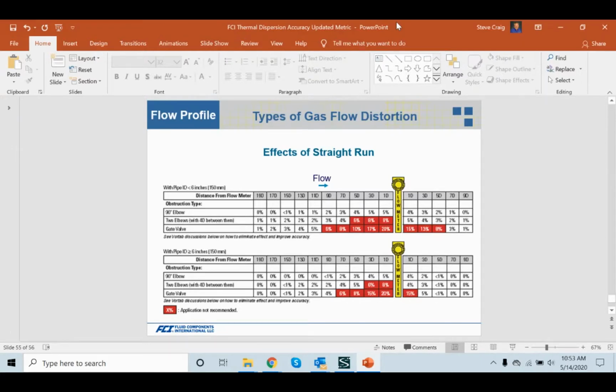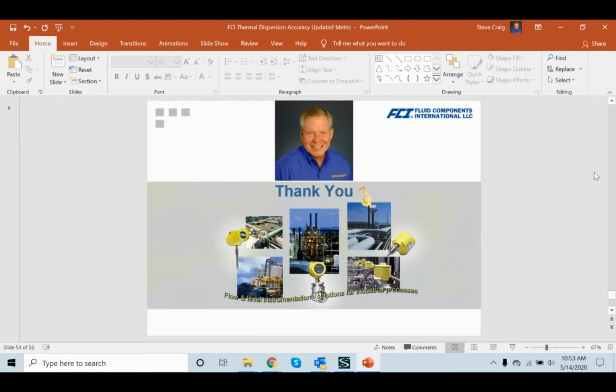And then our last question we had is, why are the electronics not potted to prevent moisture intrusion? We do put a coating on the electronics to try to eliminate moisture within the enclosure. The typical damage that occurs to the electronics is when we have a leakage through a conduit port, through a cable gland. Perfect. Yeah, via the conduit.